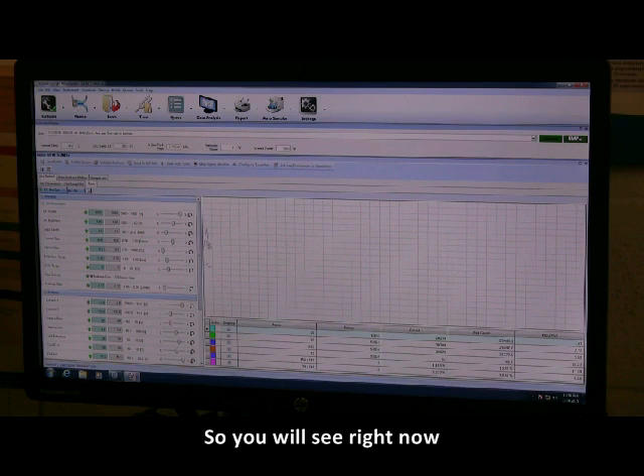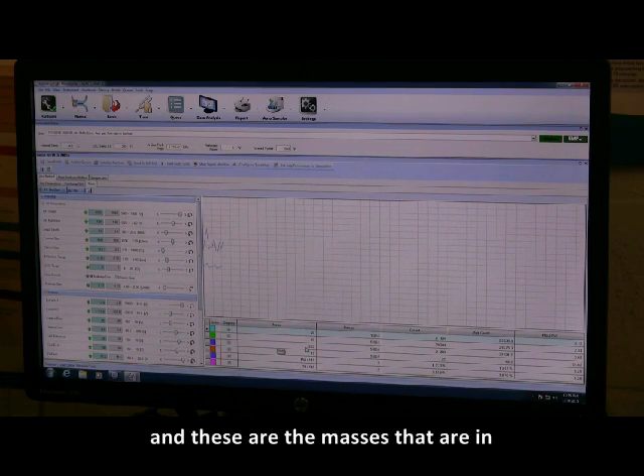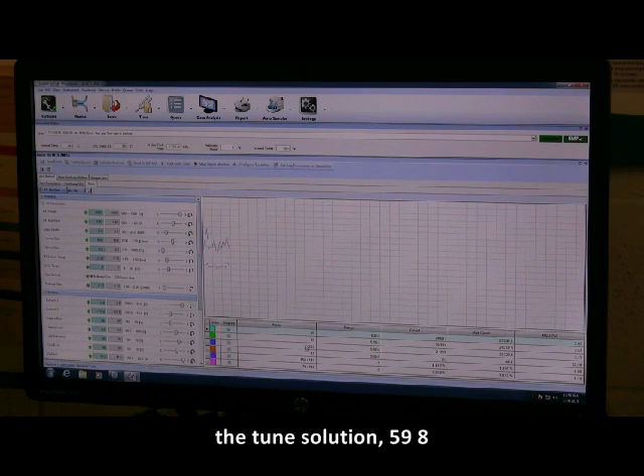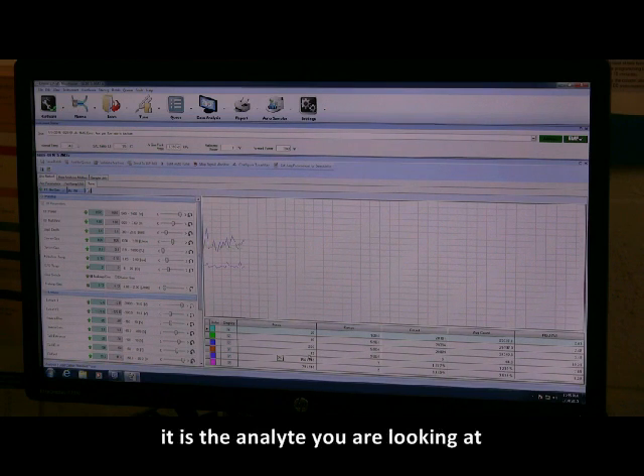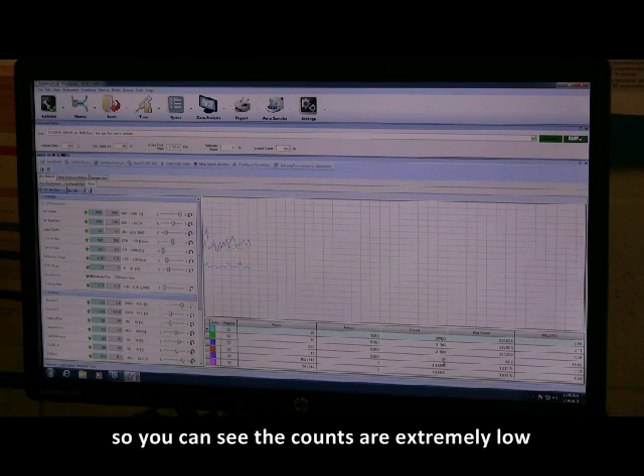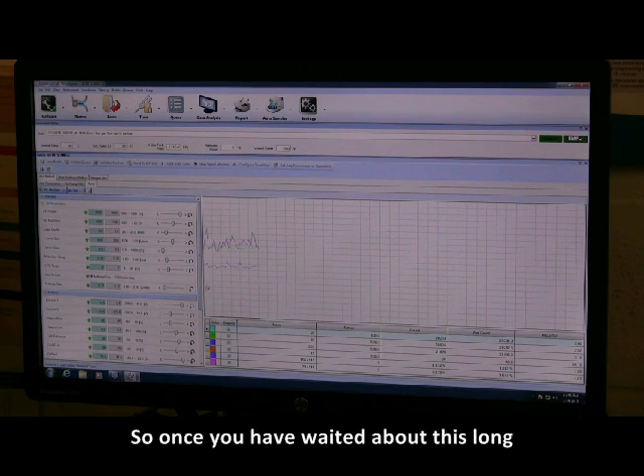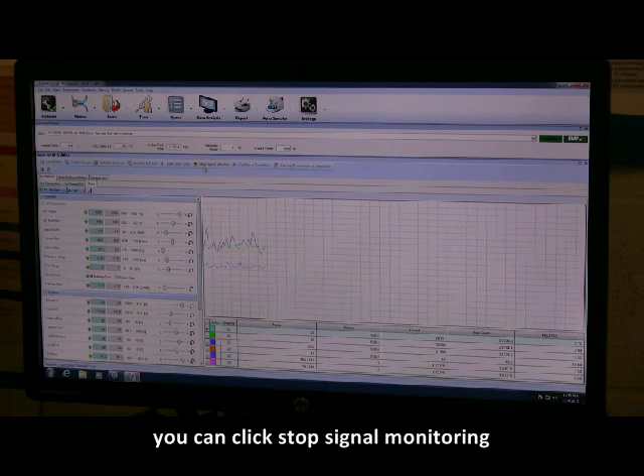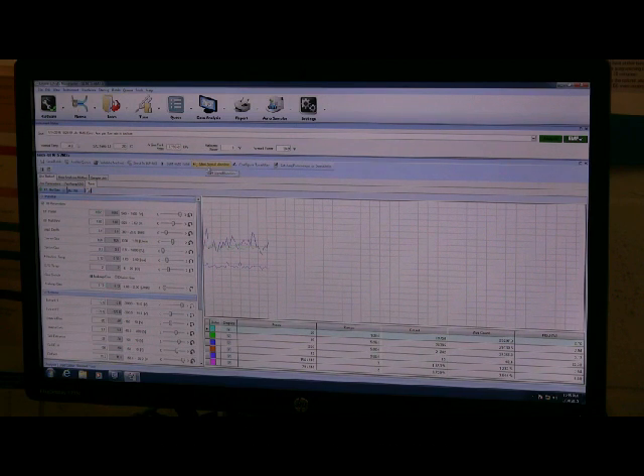So you'll see right now it's collecting data in real time, and these are the masses that are in the tune solution, 59, 89, 205. One thing you want to note, 75 is not in the tune solution, but it is the analyte that you're looking at. So you can see the counts are extremely low. So once you've waited about this long, you can say stop signal monitoring.